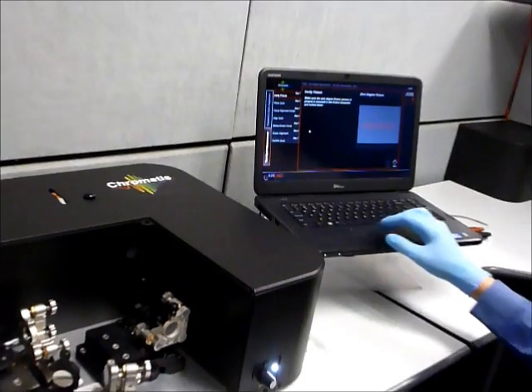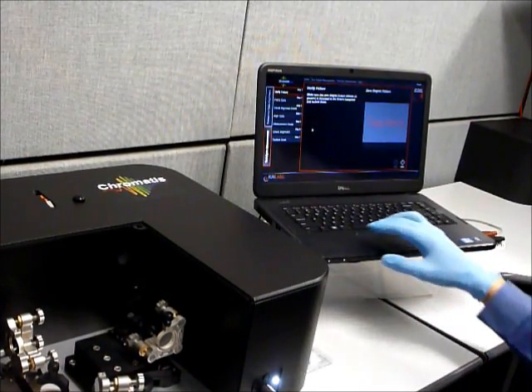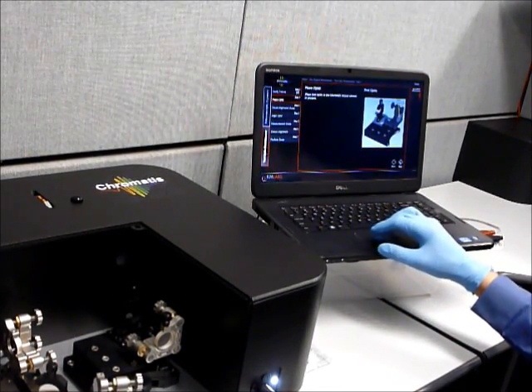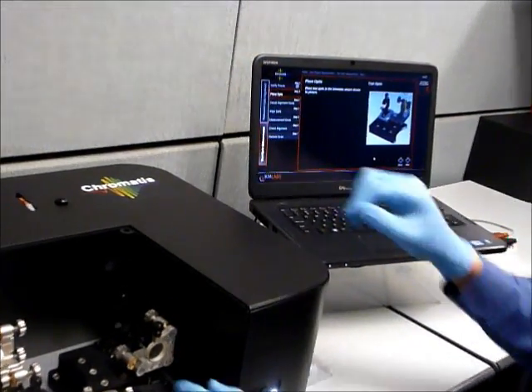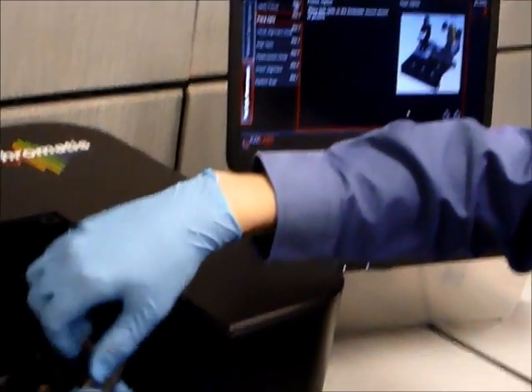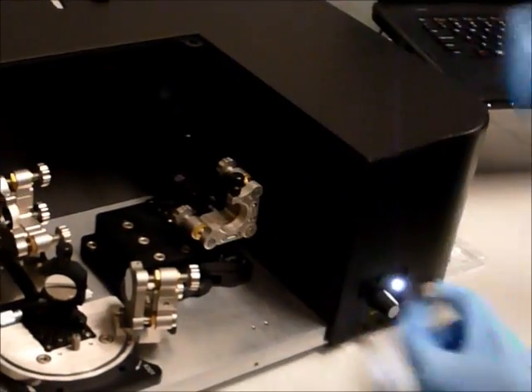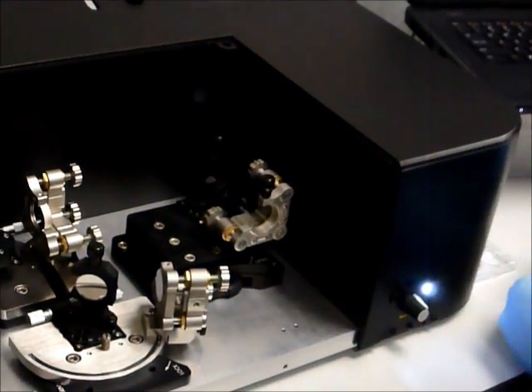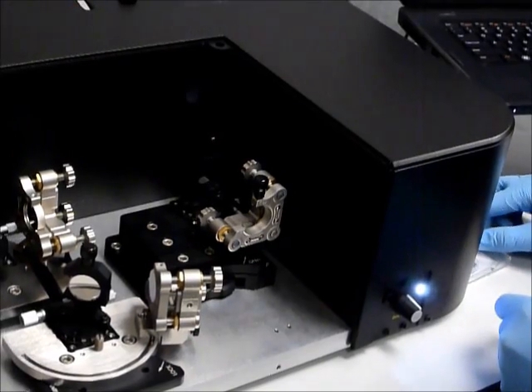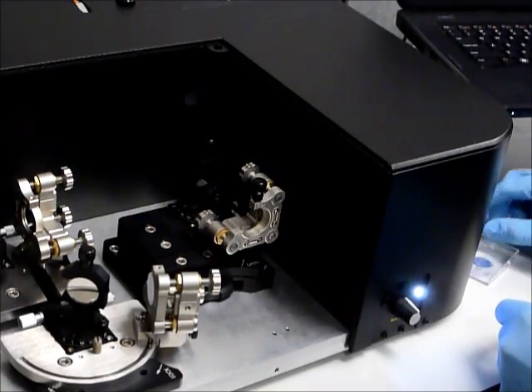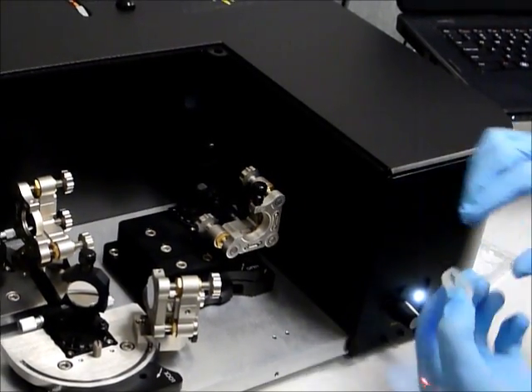So the first thing we do is make sure we have the correct fixture, and then we place the optic in the fixture. It's a very simple process. Removing the reference silver mirror and placing our mirror under test.